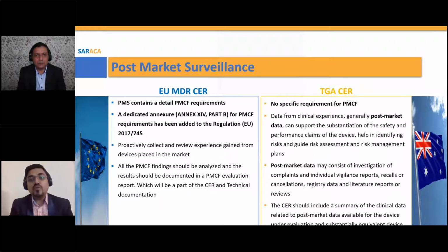Those can be an input for your PMS plan. By that PMS plan, you can further create your post-market surveillance or periodic safety update report, so that will be a part of the technical file.